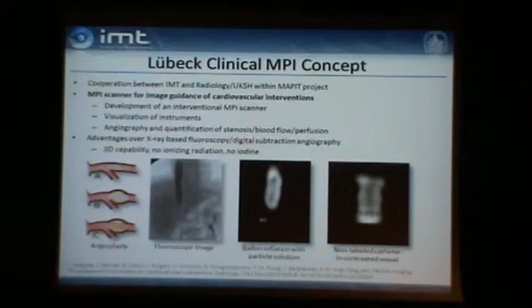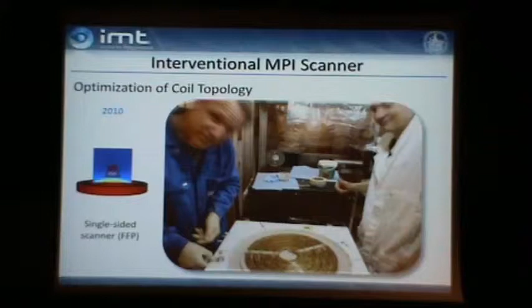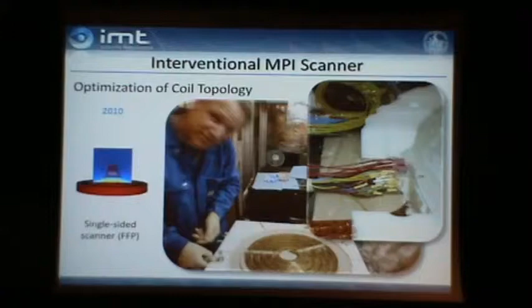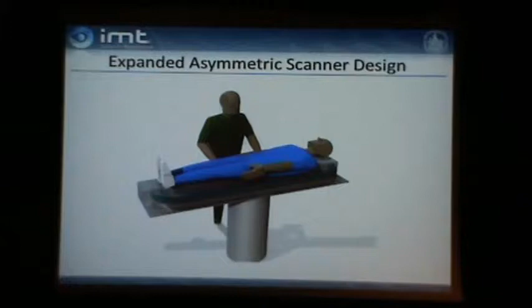And what we then first tried is a huge coil that will be integrated into the patient table. You see 2 of the technicians here, which are very crucial for this project as well. However, what we learned then, we have a lot of sensors in this kind of sandwich-like coils that we have to produce for temperature sensing, and also the field quality is single-sided in the end, which has a restriction in penetration, as I said before. And so we need huge coils to have an acceptable field of view. And from this point, we thought, okay, when we have huge coils, then the coils must be too large to fit on the patient table. Maybe this is a concept where we may introduce arena-like or elliptical coils into the patient table in the catheter lab.